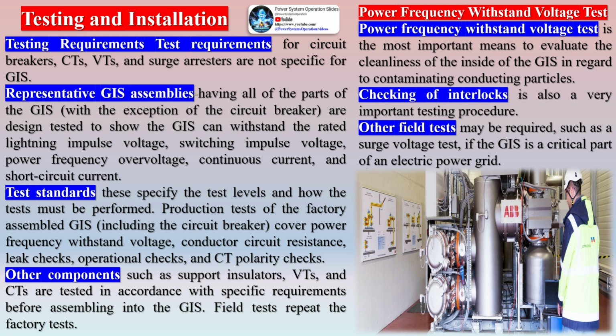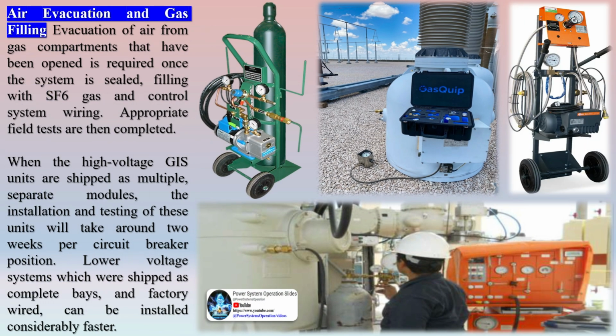Production tests of the factory assembled GIS including the circuit breaker cover power frequency withstand voltage, conductor circuit resistance, leak checks, operational checks, and CT polarity checks. Other components such as support insulators, VTs, and CTs are tested in accordance with specific requirements before assembling into the GIS. Field tests repeat the factory tests.